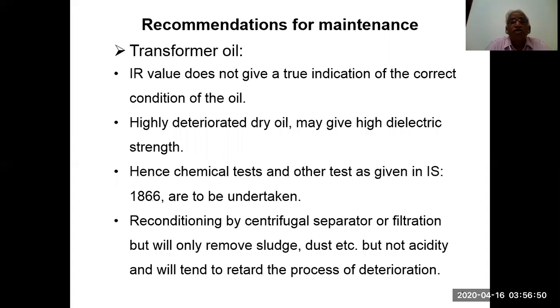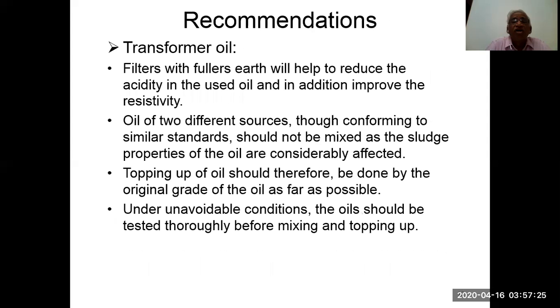Recommendations for maintenance. Transformer oil IR value does not give a true indication of the correct condition of the oil. Highly deteriorated dry oil may give a high dielectric strength. Hence, chemical tests and other tests as given in IS 1866 are to be undertaken. Reconditioning by centrifugal separator or filtration will only remove sludge, dust, etc., but not acidity, and will tend to retard the process of deterioration. Filters with the Fuller's earth will help to reduce the acidity in the used oil, and in addition improve the resistivity.